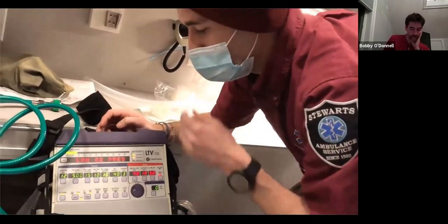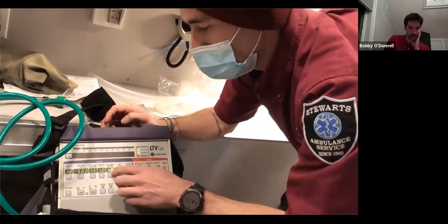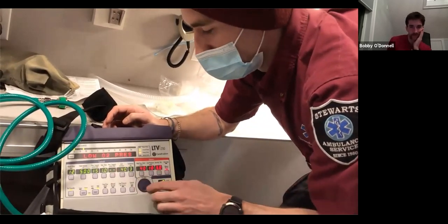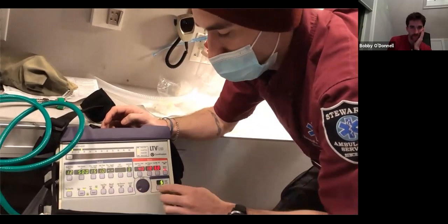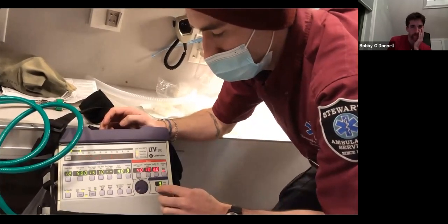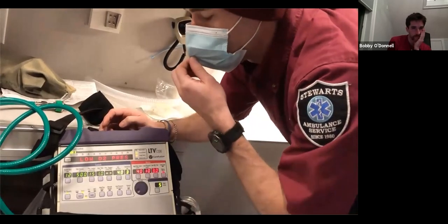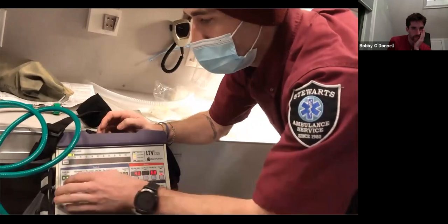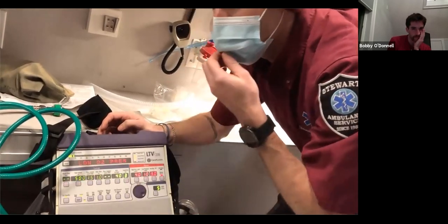Since it's CPAP, we're not going to have any pressure support, so we're highlighted here. That's going to go down to the dashes, and you hit it again to confirm. Start our PEEP at 5, or whatever is appropriate for your patient. And then the biggest thing to remember with CPAP is our breath rate is going to be down at these dashes again because it's one continuous pressure.